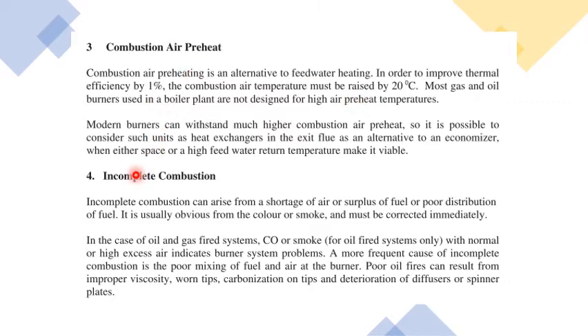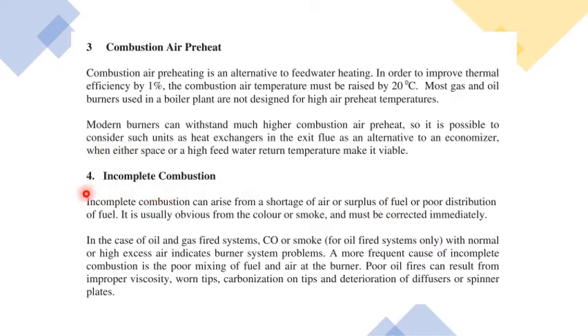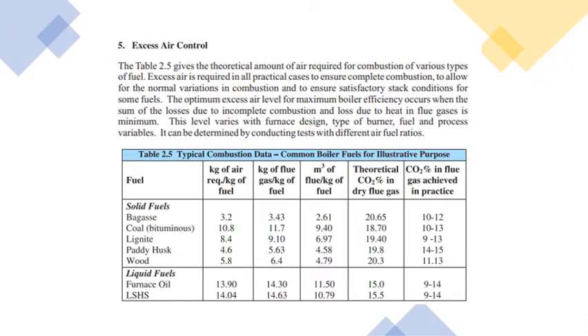The fourth point is incomplete combustion, which can arise from a shortage of air, surplus of fuel, or poor distribution of fuel. This must be avoided. In oil and gas-fired systems, carbon monoxide or smoke with normal or high excess air indicates a burner system problem. Proper air-fuel mixing must be ensured so that complete combustion occurs, which leads to better boiler efficiency.